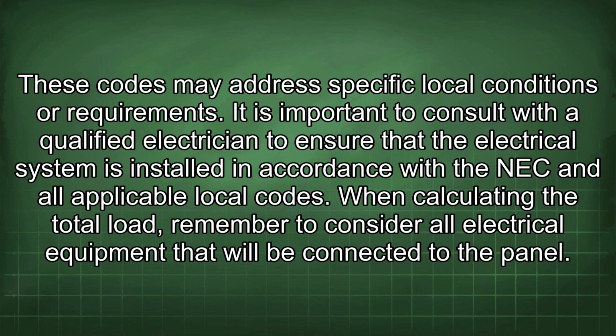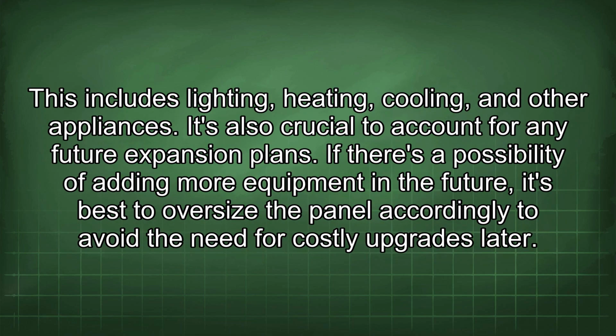When calculating the total load, remember to consider all electrical equipment that will be connected to the panel. This includes lighting, heating, cooling, and other appliances. It's also crucial to account for any future expansion plans. If there's a possibility of adding more equipment in the future, it's best to oversize the panel accordingly to avoid the need for costly upgrades later.